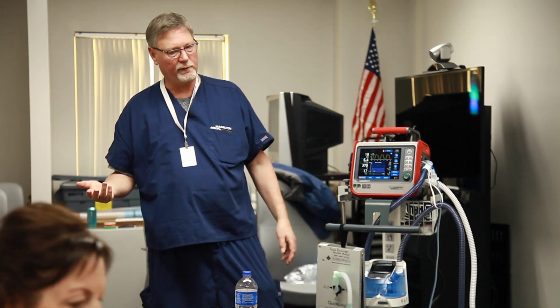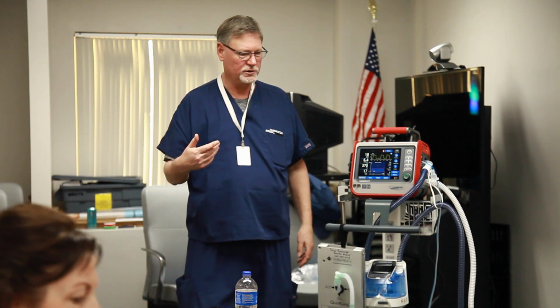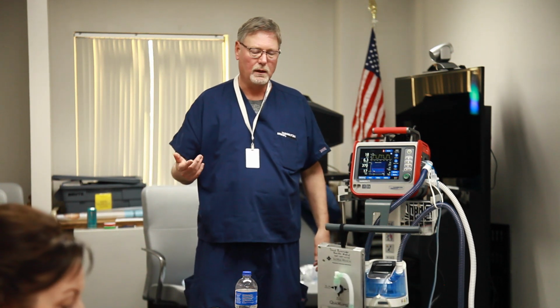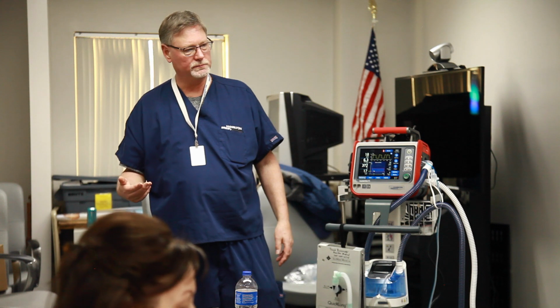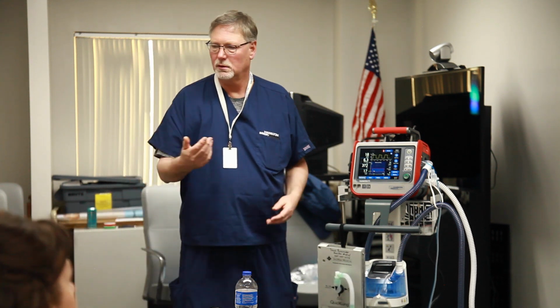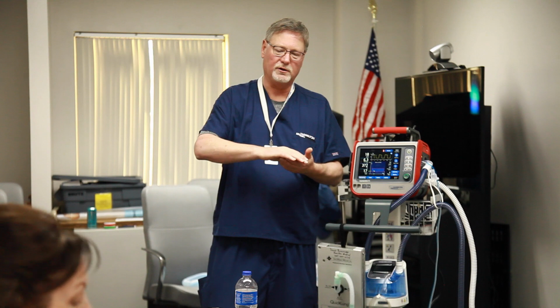With the 3.0 software that George is going to come and put in sometime, there's also something called the CPR mode that you can actually configure to an inspiratory pressure of 15, whatever we want, PEEP of 0 or PEEP of 5, 100%. It's going to spread out all your alarms, and it's just going to do ACLS guidelines of rate 10, high time of 2 seconds, and once you're intubated, you're not going to have to worry about that. Flight teams are huge on that because they don't have enough hands.